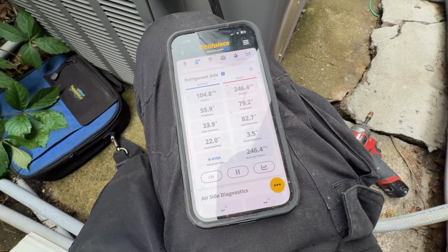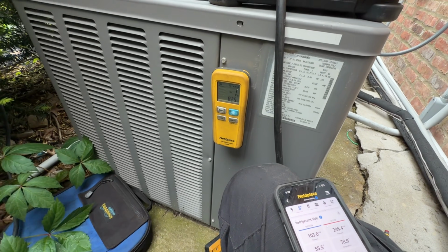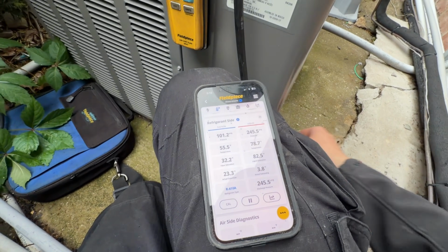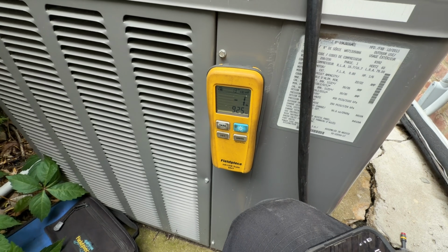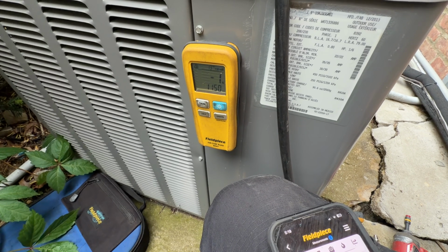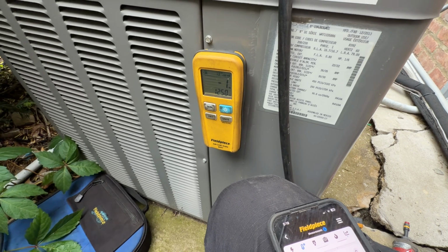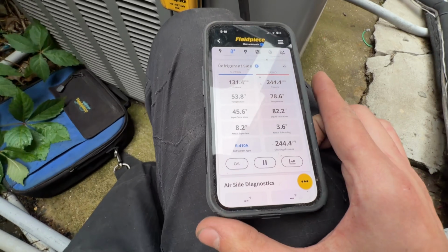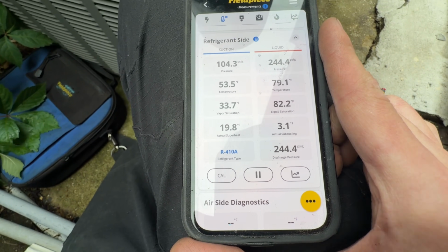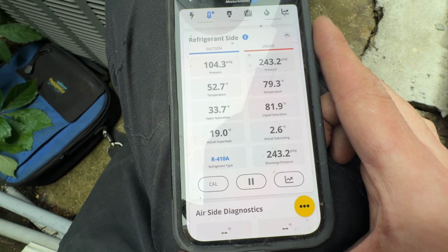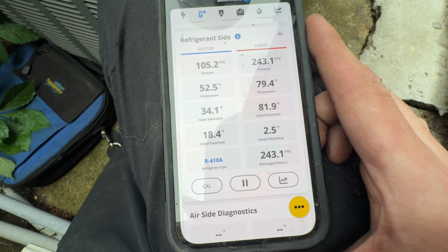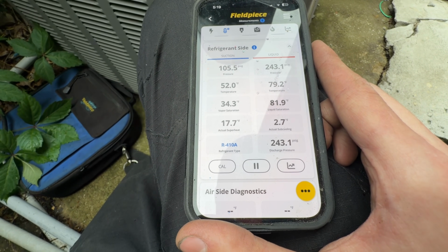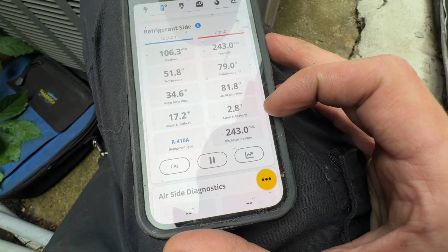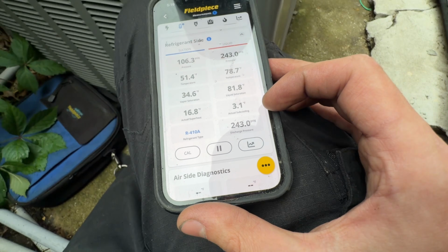Now the subcooling is starting to jump up a little bit more. We're at 1.5 pounds. I'm gonna bring it up to 2. Open the valve. Close that off and see what happens. Hopefully our subcooling starts to climb up a little bit.